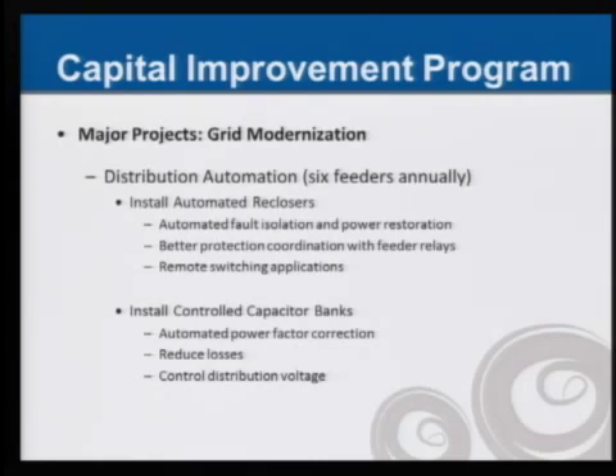Question on the installation of the automatic reclosers: in the case of a downed wire, I'd assume this might require some public education. A downed wire might appear de-energized on visual inspection, but if we reclose automatically, it could re-energize while it's still down. Is that correct? And if so, are there any thoughts about a public education campaign for our customers to address the issue?